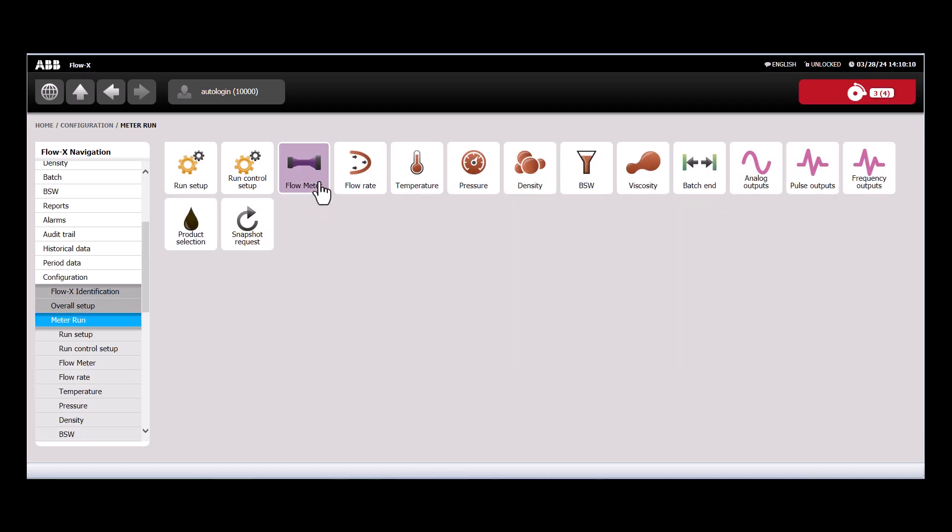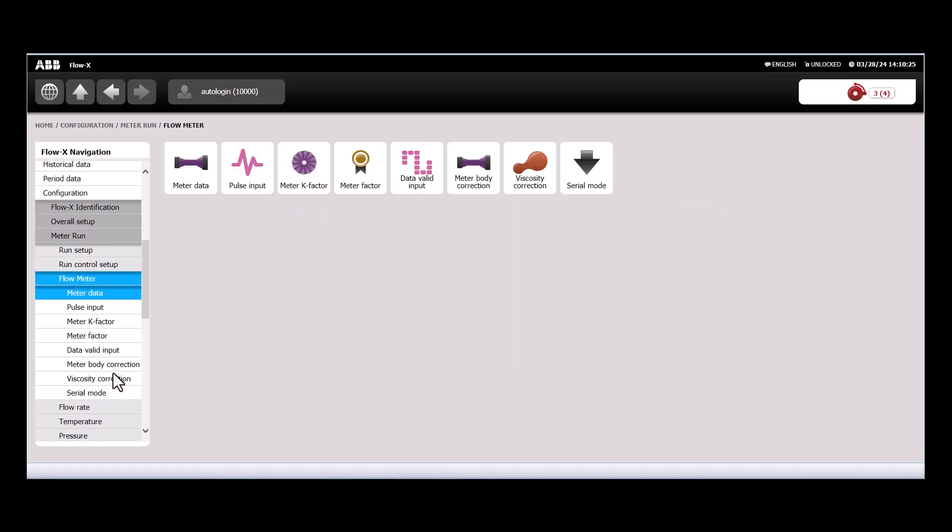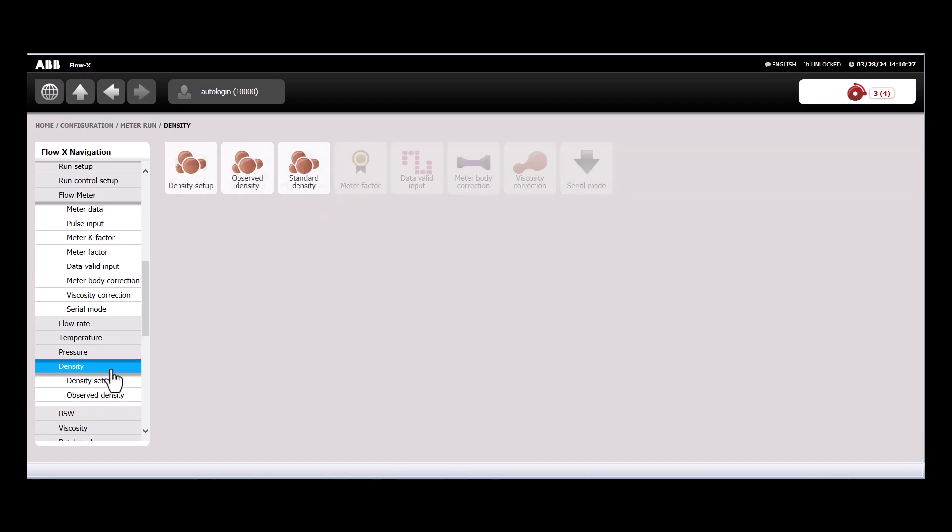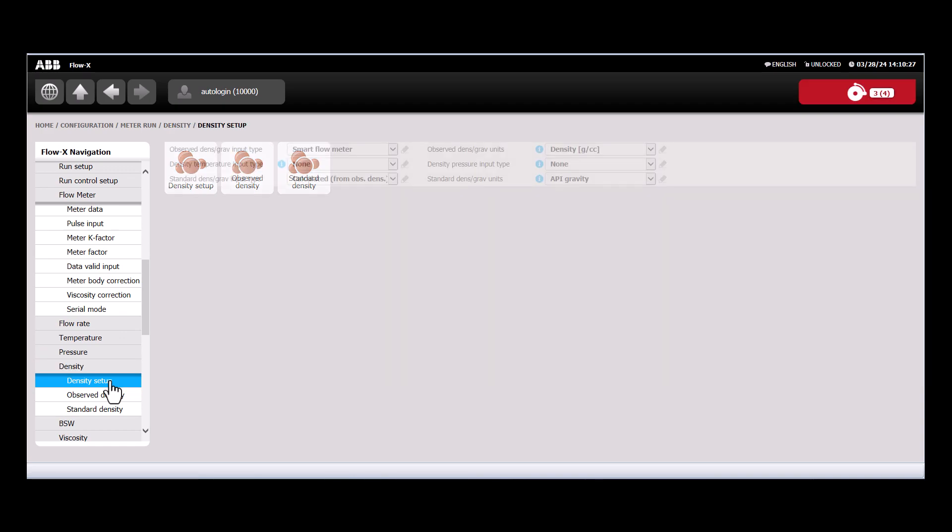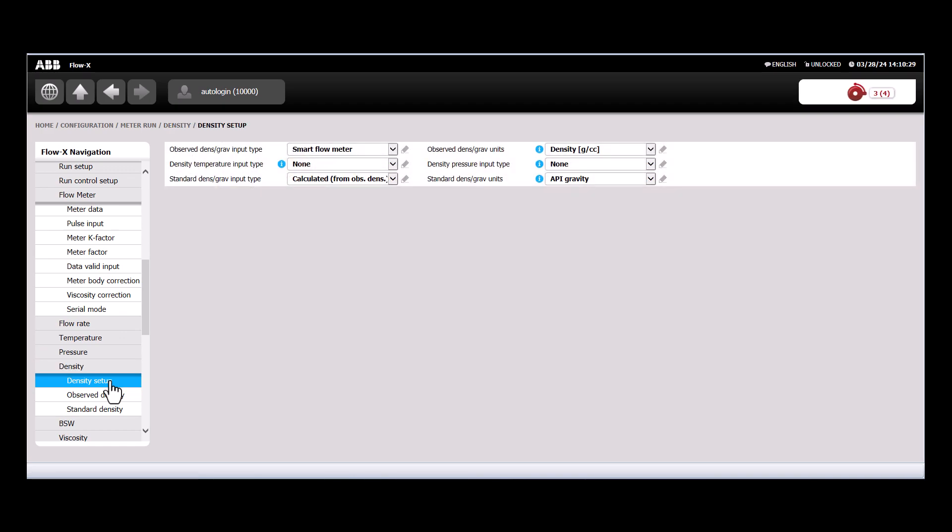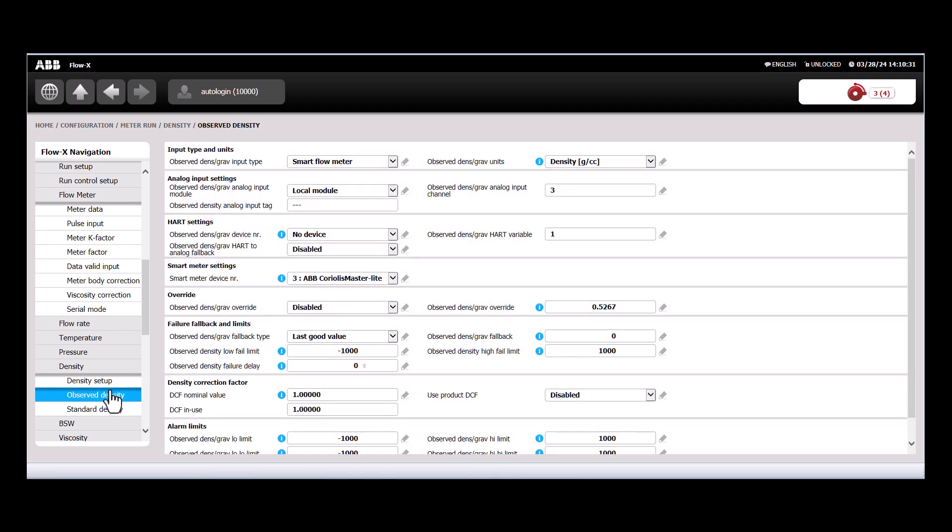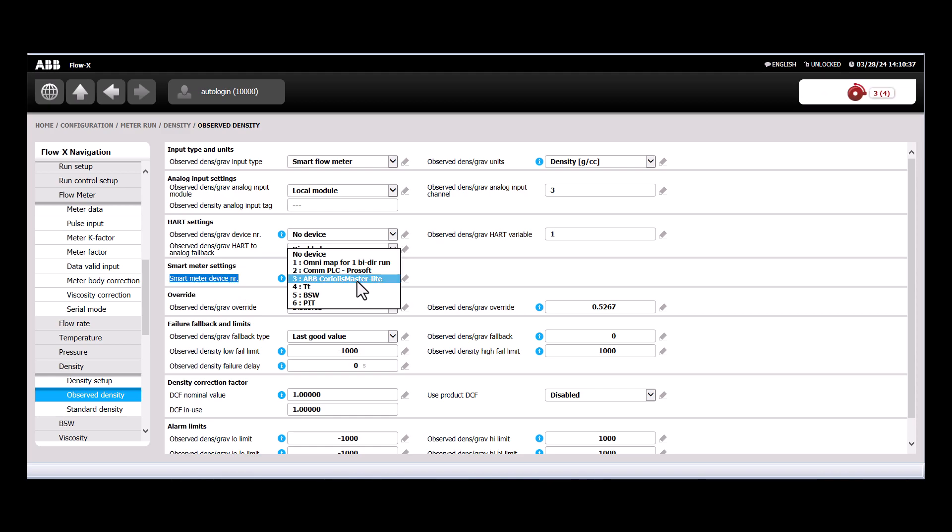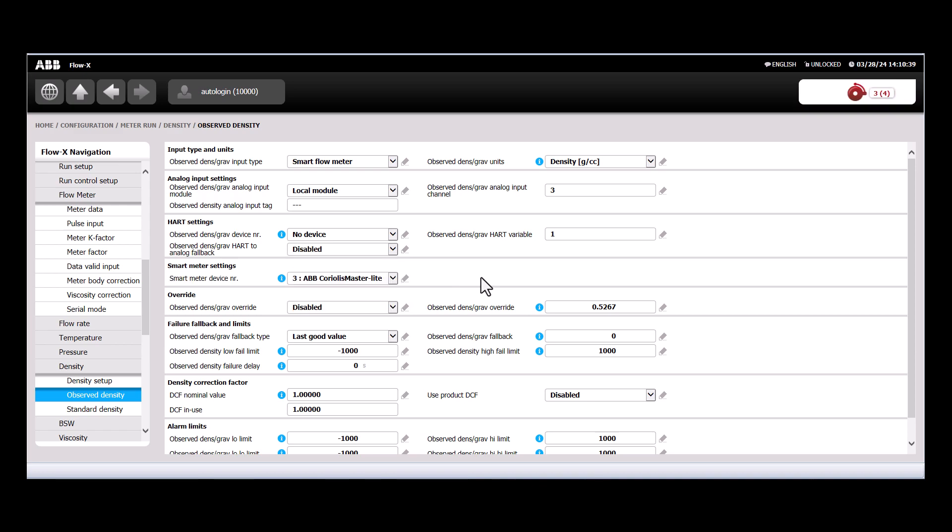We'll go to the meter run, we'll go to the flow meter, and then we'll go down to density. We'll verify that we're using a smart flow meter, and then we'll go to observe density, and just validate that the smart meter device number is equal to the communication sheet we just loaded in.